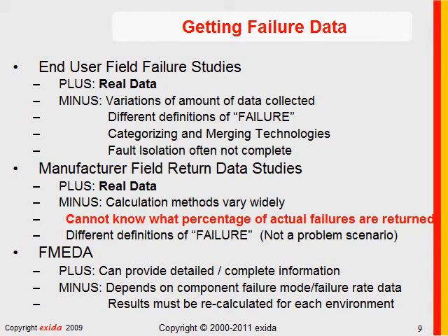We looked at those numbers and we thought, wow, we are great, and it made us feel good, but it doesn't mean they're right, and it doesn't mean you should be using these kind of numbers to do safety validation calculations. A manufacturer cannot know for sure what percentage of actual failures are being returned unless there's some metric, or unless the manufacturer takes care of all service and maintenance via contract. And manufacturers have different definitions of what is a failure.